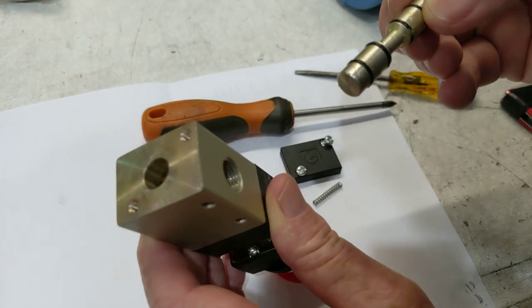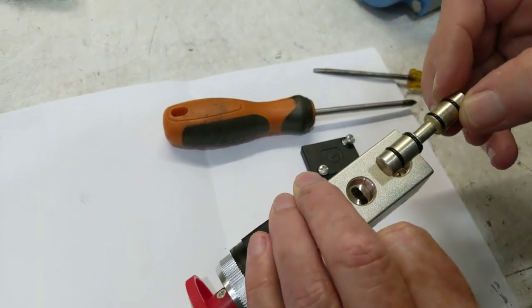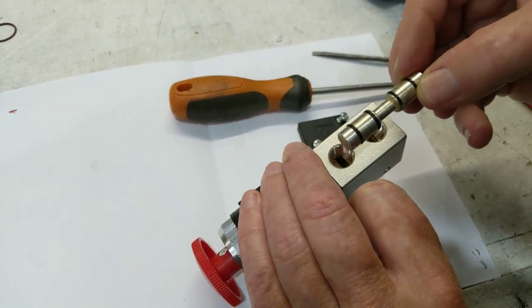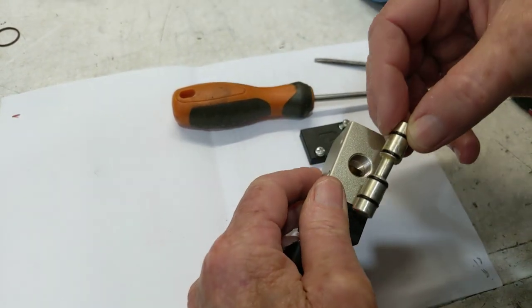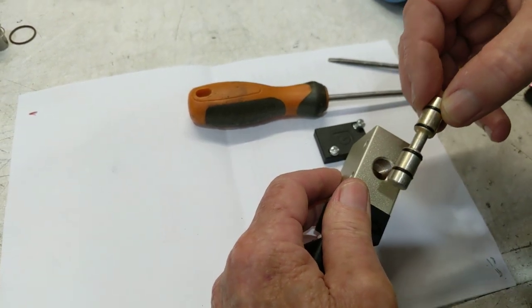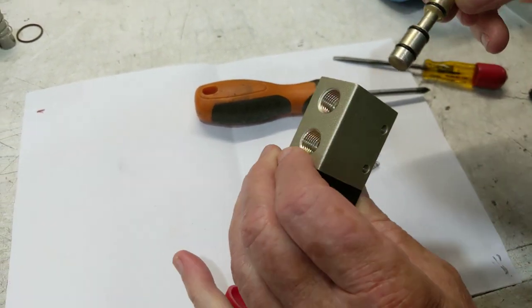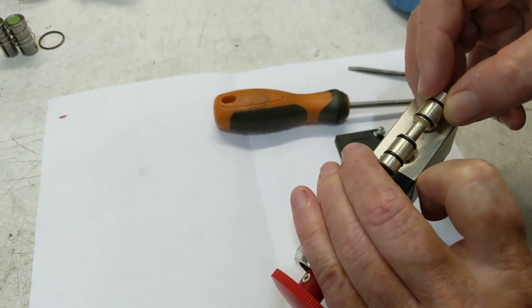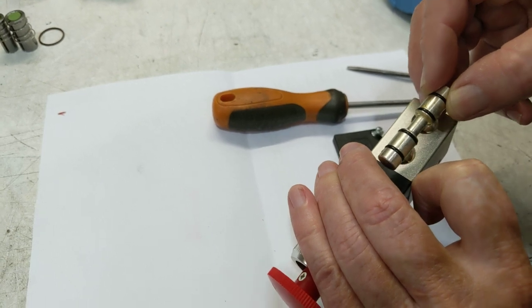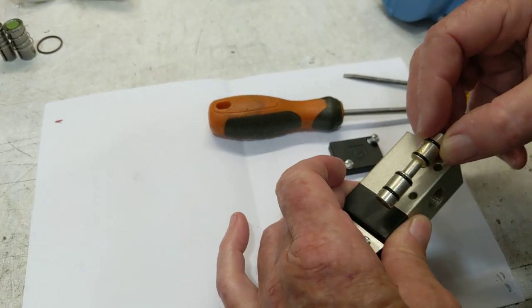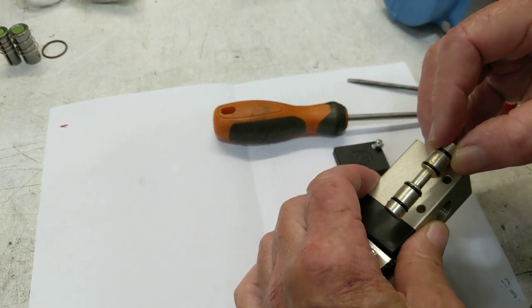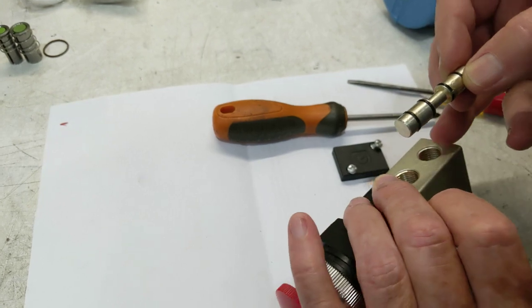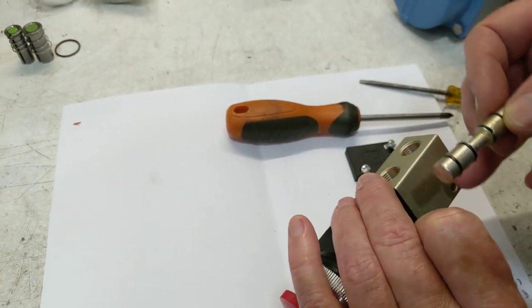Take the valve again and push it back in. The actual way this unit operates is that the o-rings move across the ports like this to direct the air in through the three ports. It moves across that port there like that. That's how the flow is directed between this center bit which moves that way, and when it comes back it moves to this side here, directing the air from the center to the top port or to the center back down to the inlet port, so the inlet port is supplying both exhaust and cylinder.